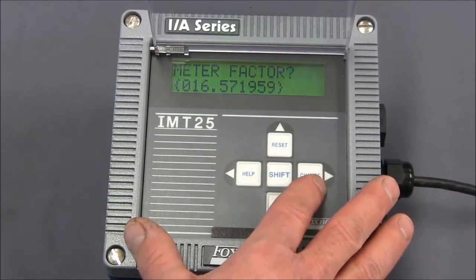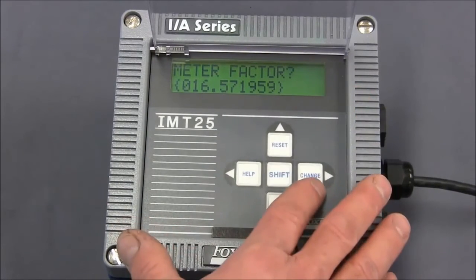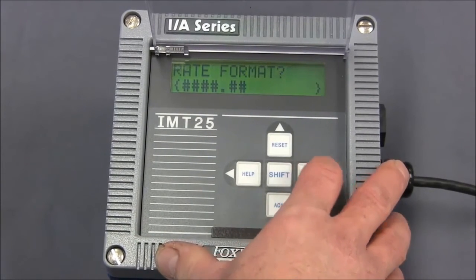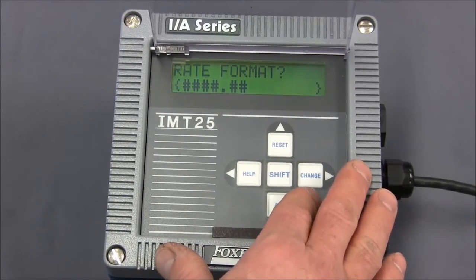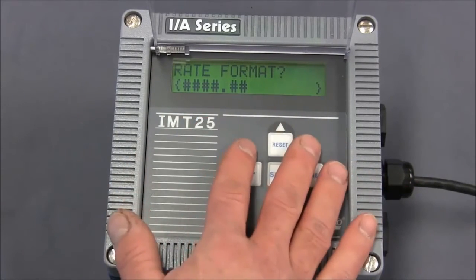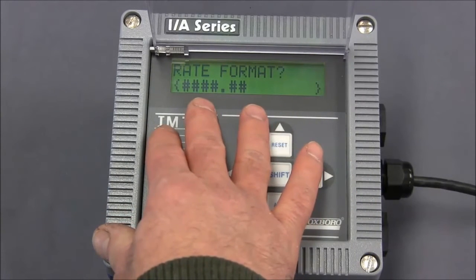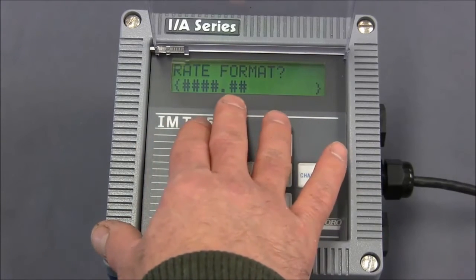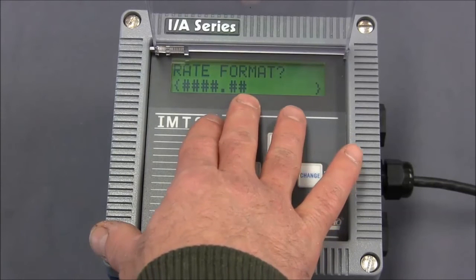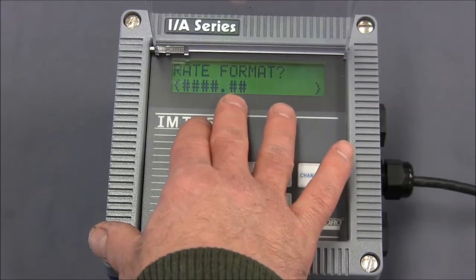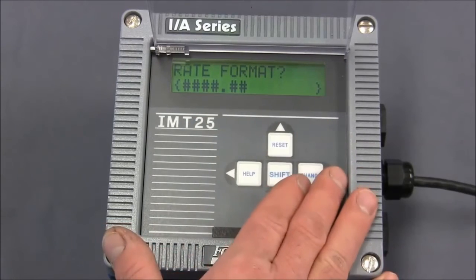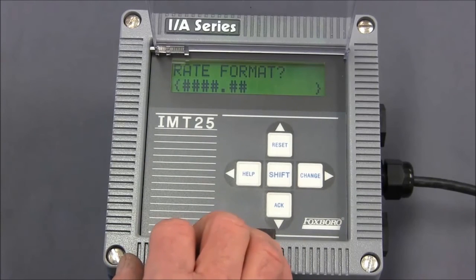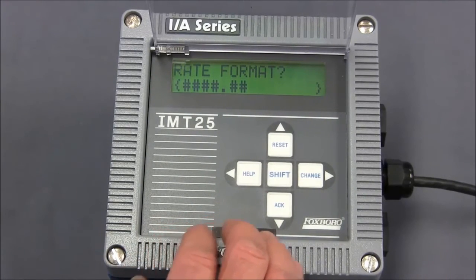Sometimes you'll find the last couple of digits may change slightly. This will have no impact on the measurement. We'll go to the right. Here we have the rate format. Here you can determine when you're looking at the flow rate on the measurement screen how many fractions of a gallon you see. In this instance we can see tenths and one hundredths of a gallon. Many times on larger flow tubes people really don't care about seeing fractions of gallons and many times prefer to see just whole gallons. For this exercise we'll look at one decimal point to the right.